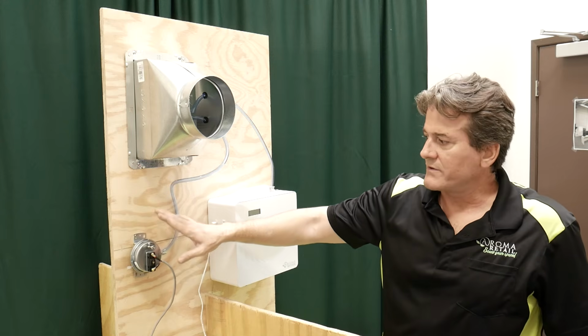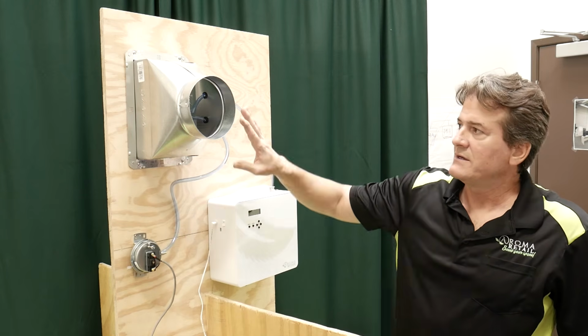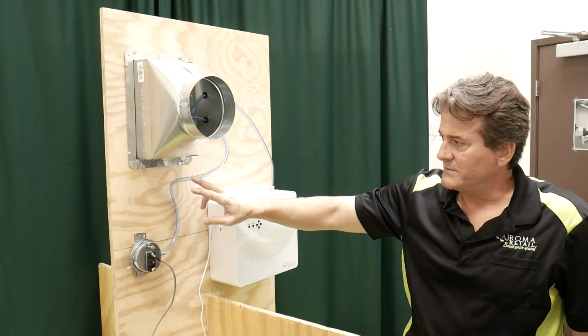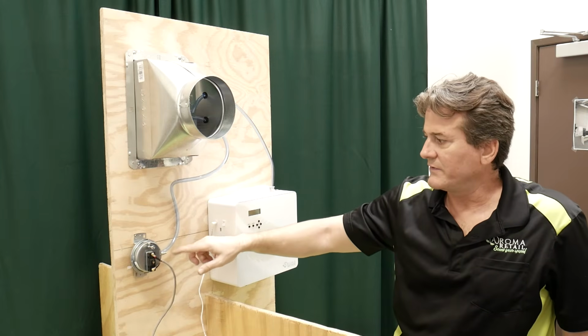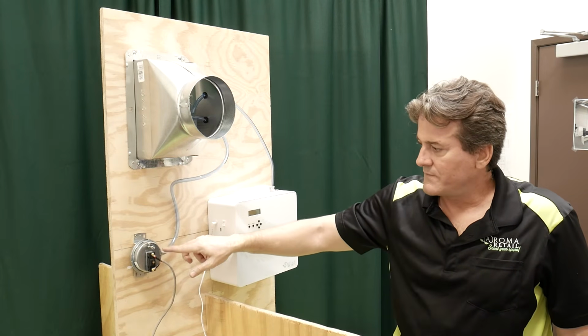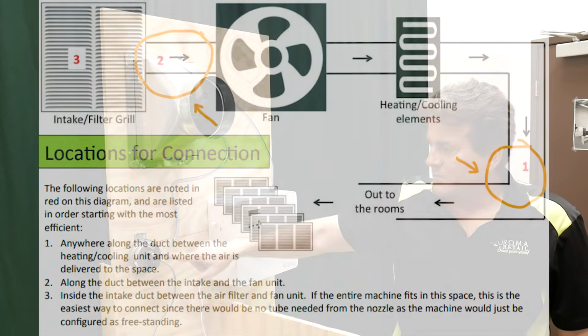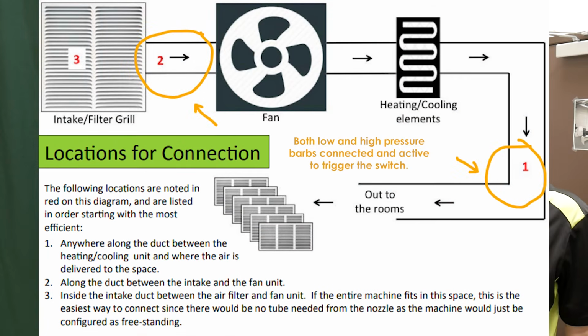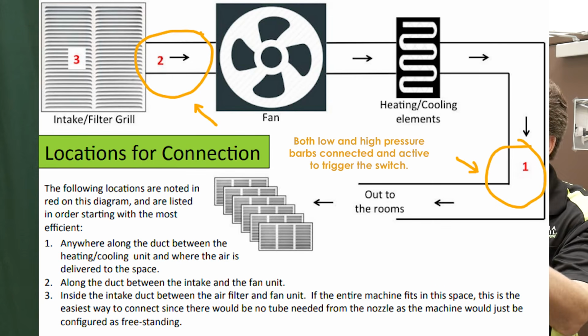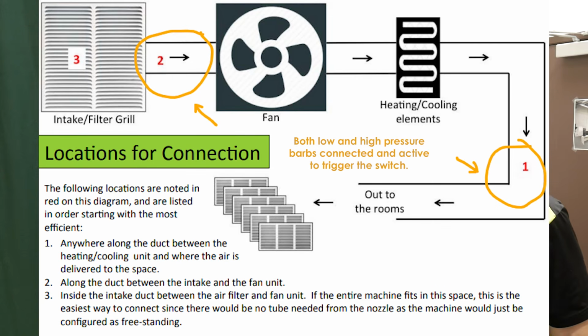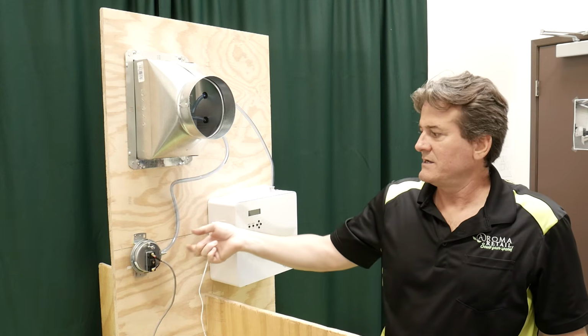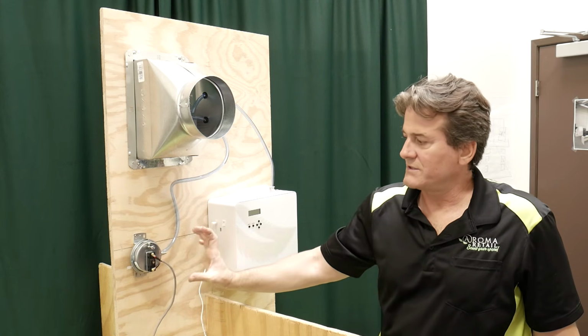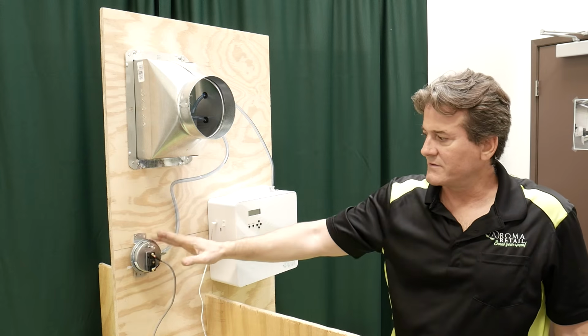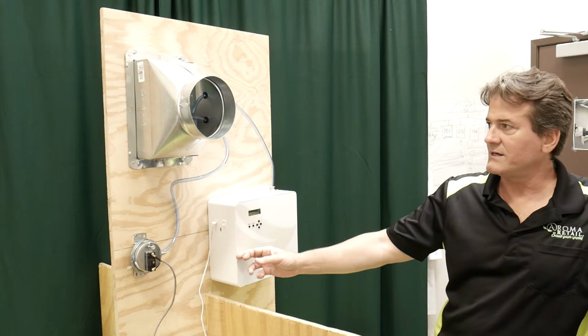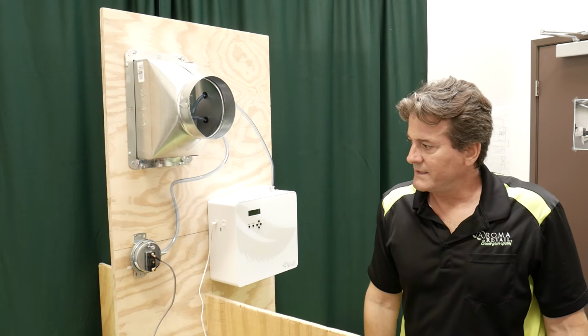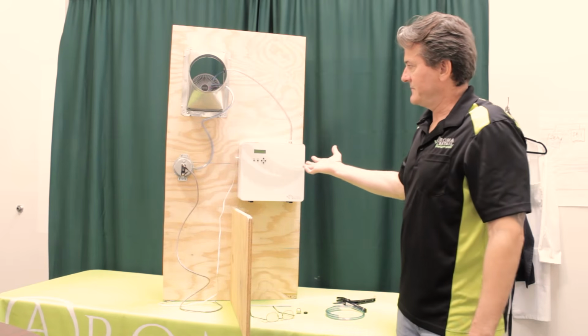If you're having a problem with your air switch not being strong enough, I would suggest running another tube. This is standard 3/8 tube. You can get it at Home Depot, or we can provide it for you. I would run another tube from the low pressure side to wherever you put your filter and go between your filter and the fan. So now the low pressure side is pulling on the switch and the high pressure side is pushing on the switch, and that should get that air switch triggered so that it can properly tell your machine when you have air in the duct. And that's it. It's as simple as that.